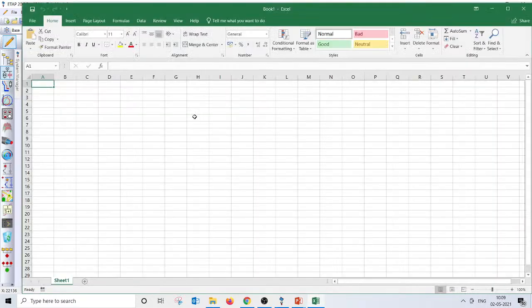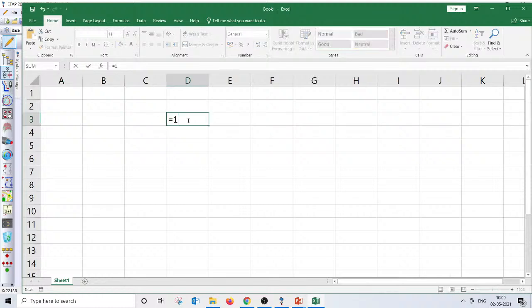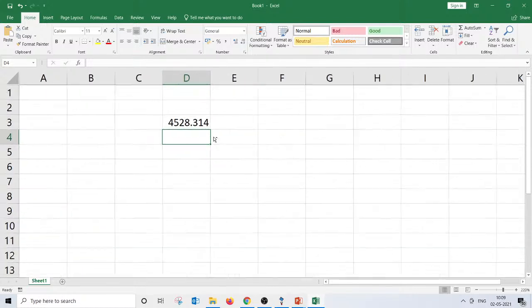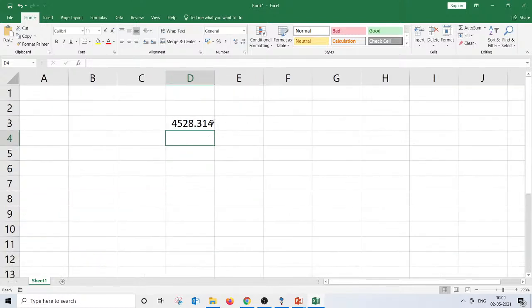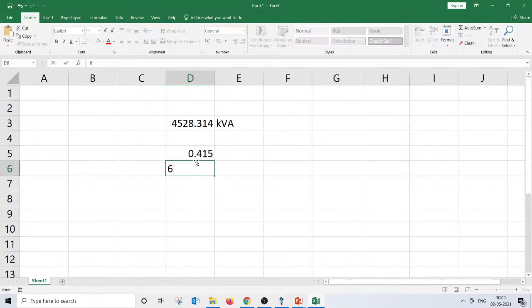So let me go to an Excel sheet and address what could be the approximate or the maximum transformer rating which can be connected, if it is 415 volts. I have taken the example of 415 volts. Is 4.5 MVA the theoretical maximum transformer rating in kVA which we can go to, correct? So I have put root 3 into voltage into current, that gives the kVA. I can put in the numbers like 415 volt, and the current, and multiply these amps. So I am trying to find out the kVA.